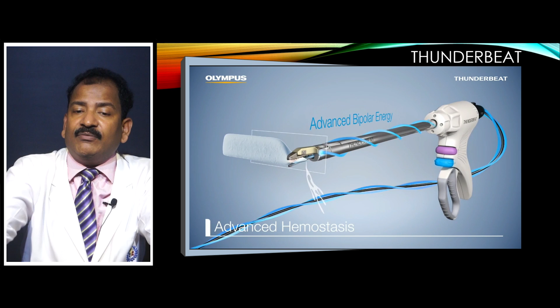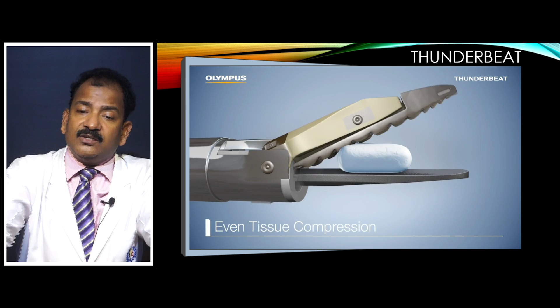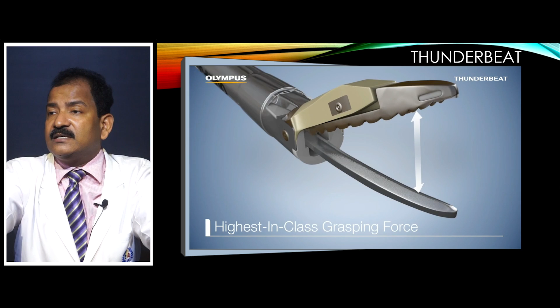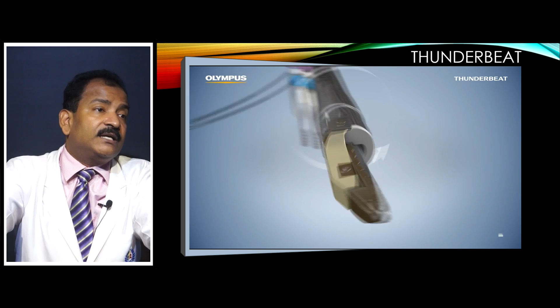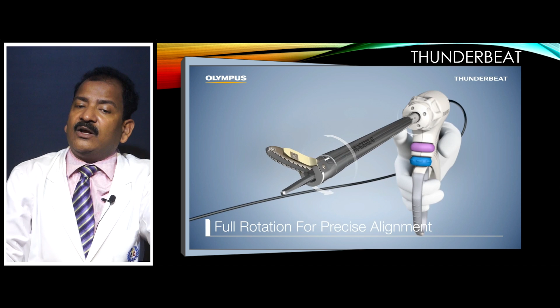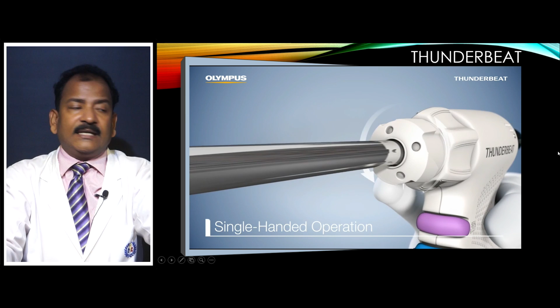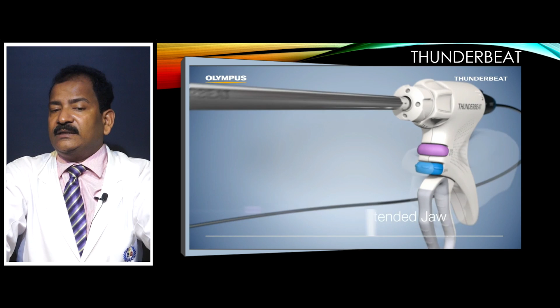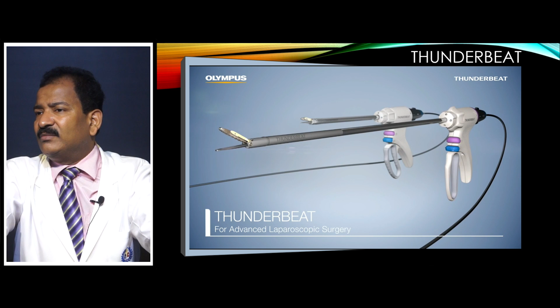Scissors are not required, vessel sealer is not required, and it has adaptive advanced bipolar energy which can talk with the tissue, and this is a probe of harmonic which can vibrate. So, it can seal vessels up to 7 millimeter with confidence, and jaw opening and pressure are controlled electronically. So, you have full rotation, articulation in every direction, and complete control on the vessel as well as dissection. Single handed operation is there, but the only drawback of this instrument is that it is strictly single use. This is one big problem. After one use, the electrode does not work.